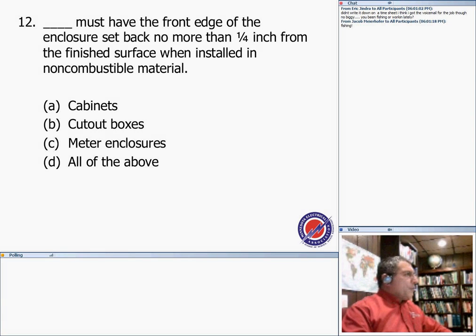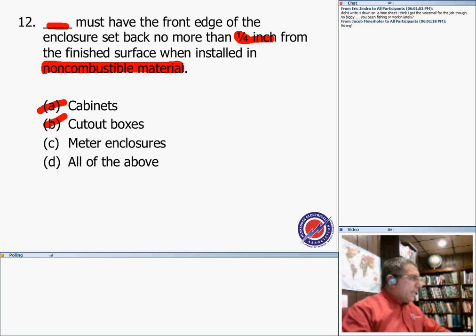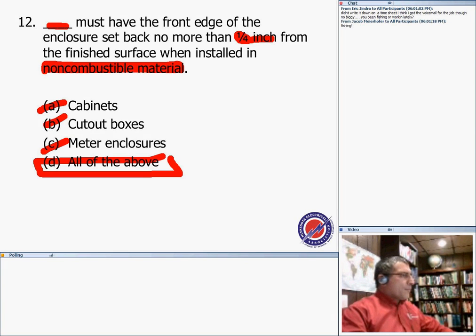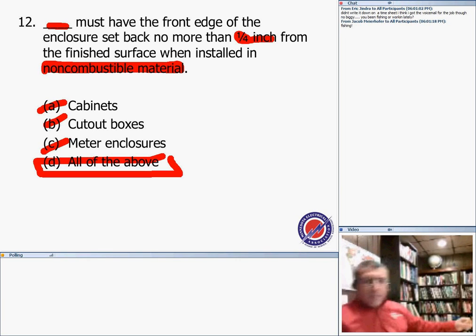Number 12. If the enclosure sits back not more than 1/4 of an inch from a finished surface installed in non-combustible material like concrete, block, tile, know that this rule applies for a lot of things, guys, for boxes and so forth. So this applies to each and every one of them. And some of you guys got that wrong. So basically for panelboards, cutout boxes, meter enclosures, even pull boxes and J boxes and especially device boxes. So our answer for this particular one was D. Any questions, guys?